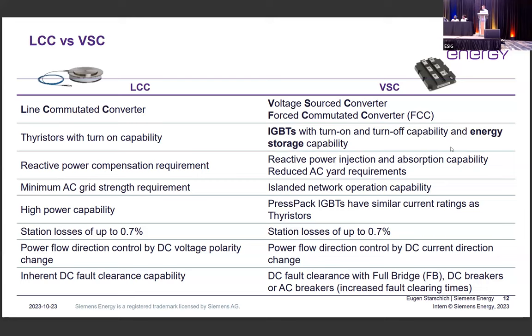One thing to also mention here, which is very important: you don't need HVDC circuit breakers for HVDC lines, for individual lines. You need them for a meshed DC grid. For a DC line, you just have AC circuit breakers on the other side of the inverters, and they can clear the fault just like an AC breaker does. But it's really the mesh configurations, where you need to isolate one DC element from another DC element, where DC circuit breakers have an advantage. There are a lot of these multi-terminal setups now being planned in Europe, but I think the initial phase of that multi-terminal is two HVDC lines that are later linked together. And at that later point, when you link them together into a network, that's when you need DC circuit breakers, but you don't really need them before then.